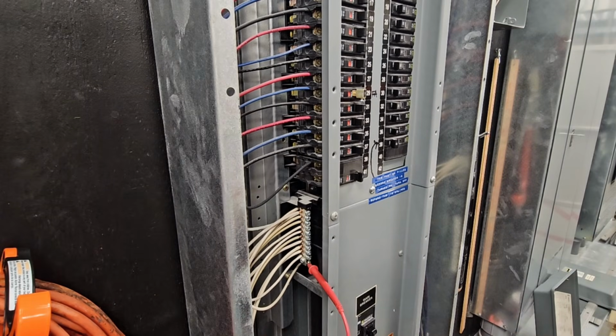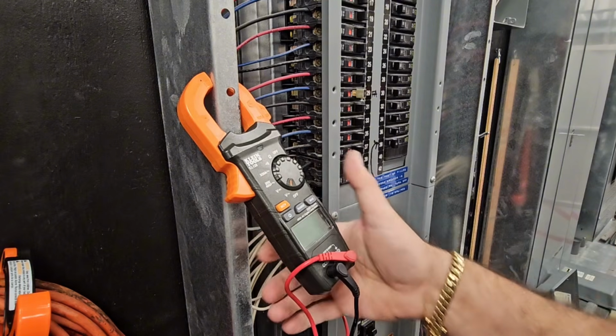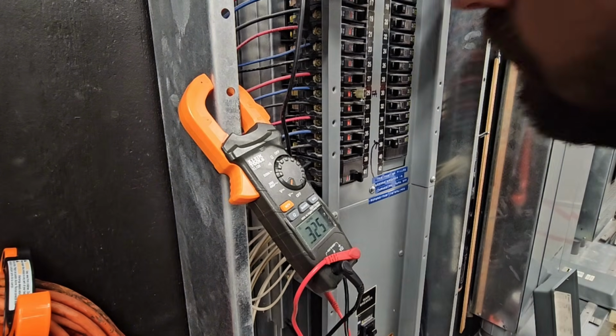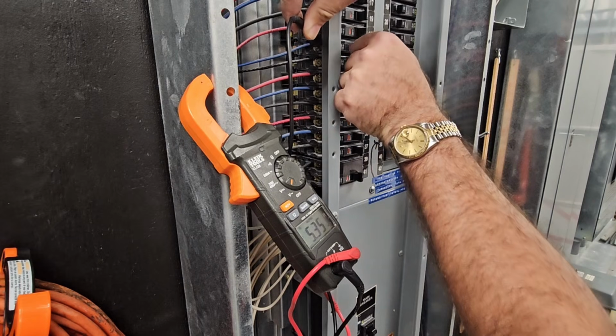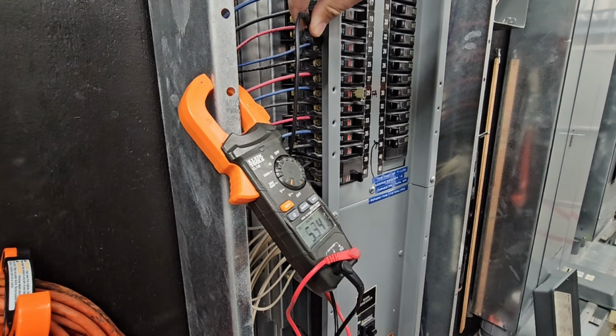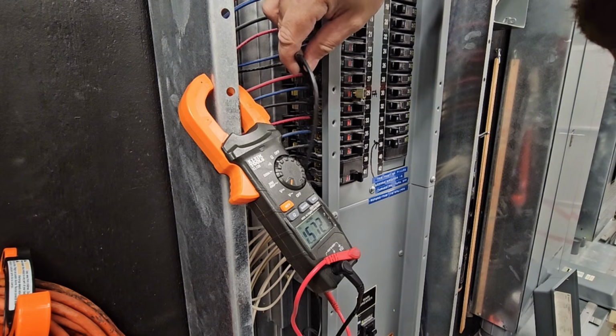And right here, I'm jamming my tester probe into the neutral bar, so I'm going to sit there and hold that one. Same story, 5 volts. But let's cycle the breaker and see what happens. Nothing, 5.3 volts. Now it's time to confirm my theory, and I'm going to check C-leg on other breakers.